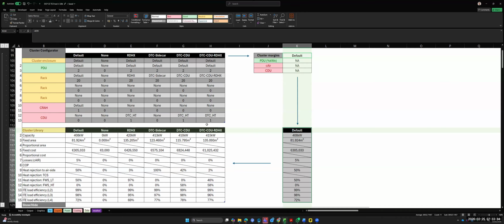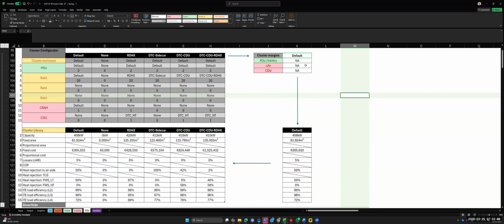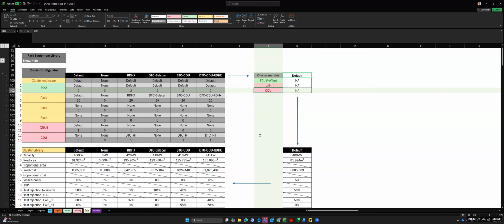Is there a precondition that the bottleneck is on the TCS side, or are both FWS and TCS sides variable? So this is the TCS - let's talk about this. We're at the cluster level here. So basically, it's saying all the heat received by the CDU via TCS has to be within the capacity of the CDU type and number you've configured. Right, so that's what that box does.